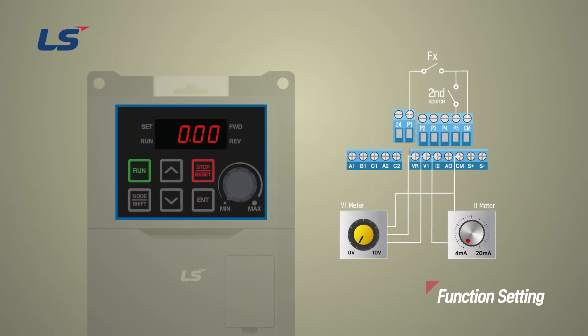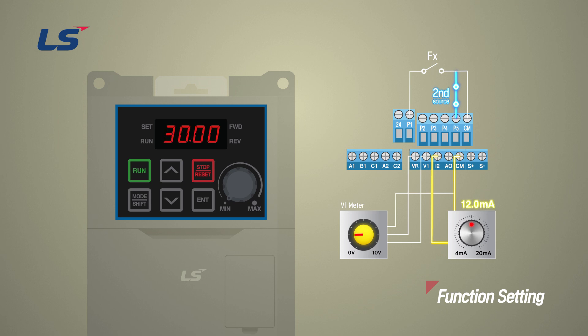When the switch of P5 terminal is in the OFF state, it operates in the original operation state which we set in DRV and FRQ. The frequency is displayed according to the voltage setting because the operation command in the original operation state is set to the terminal block and the frequency command is set to 0 to 10 volts. Since it is set as a voltage command, the frequency according to the voltage setting is displayed. If the switch of P5 terminal is changed to ON state, it operates in the second operation state.